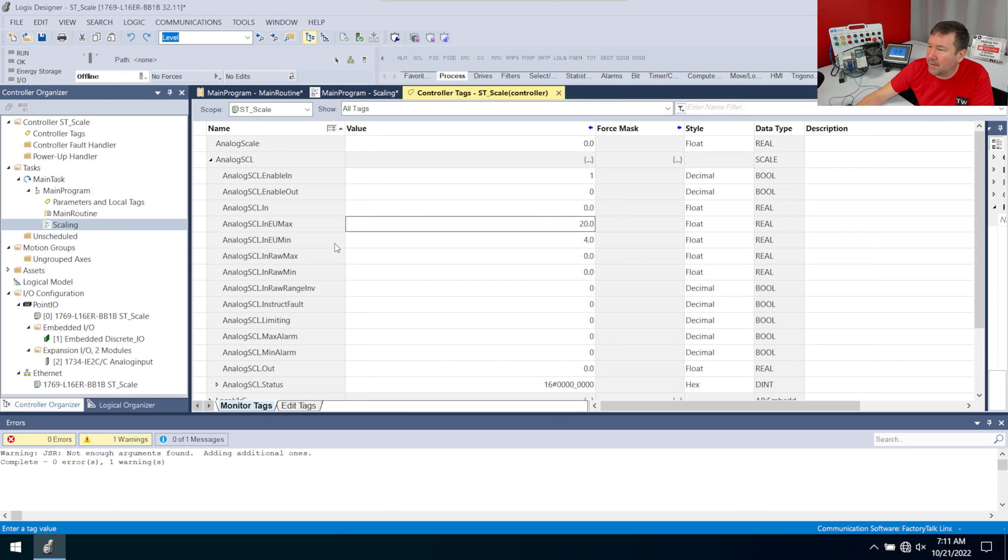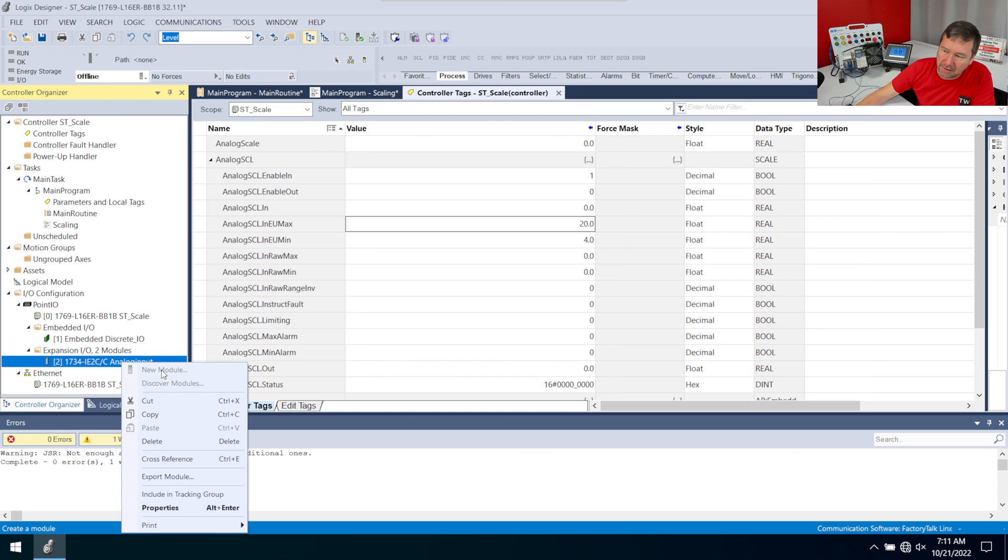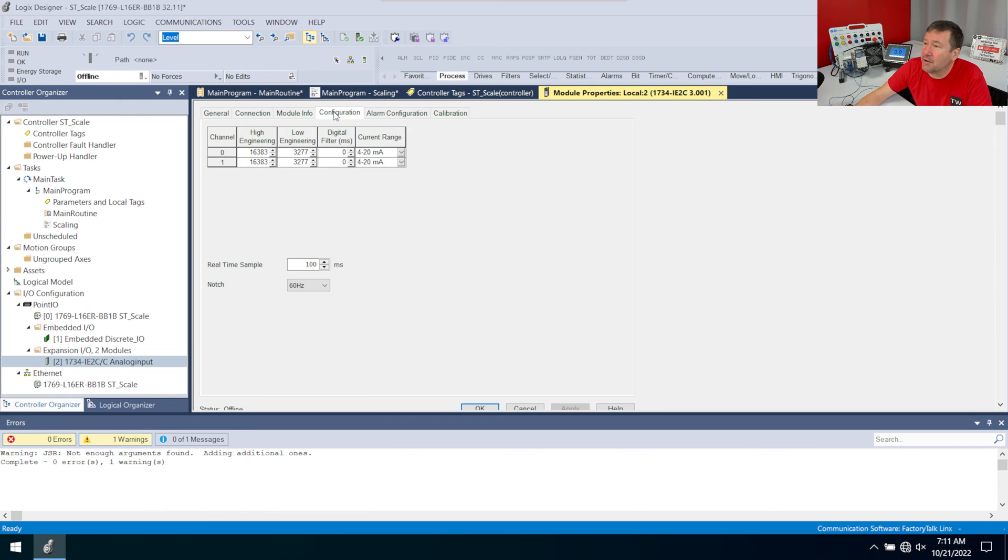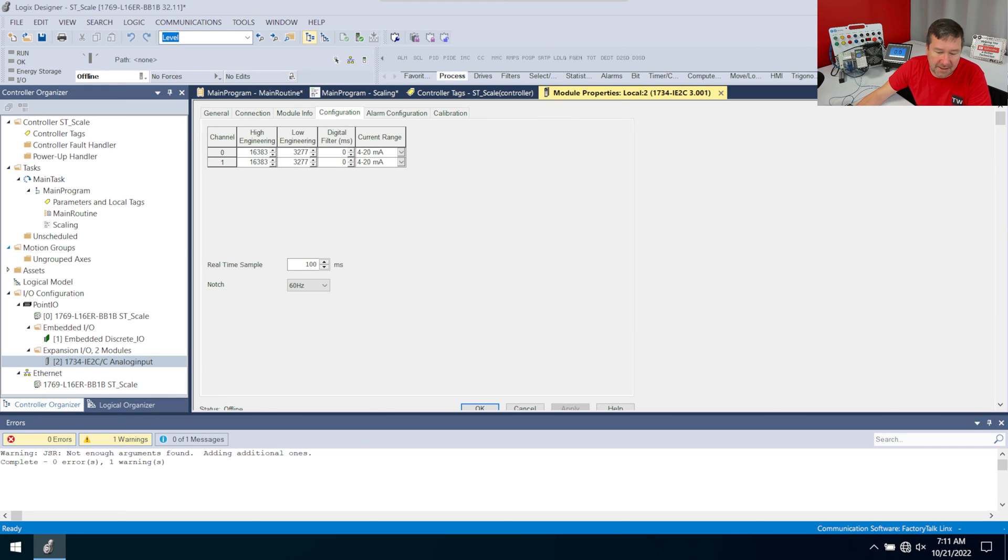And then we need our raw values. And this is something they do really well in Studio 5000 is all we need to do is right click our analog module and properties. And then we're going to go to the configuration tab. And right here is our low engineering and high engineering units.